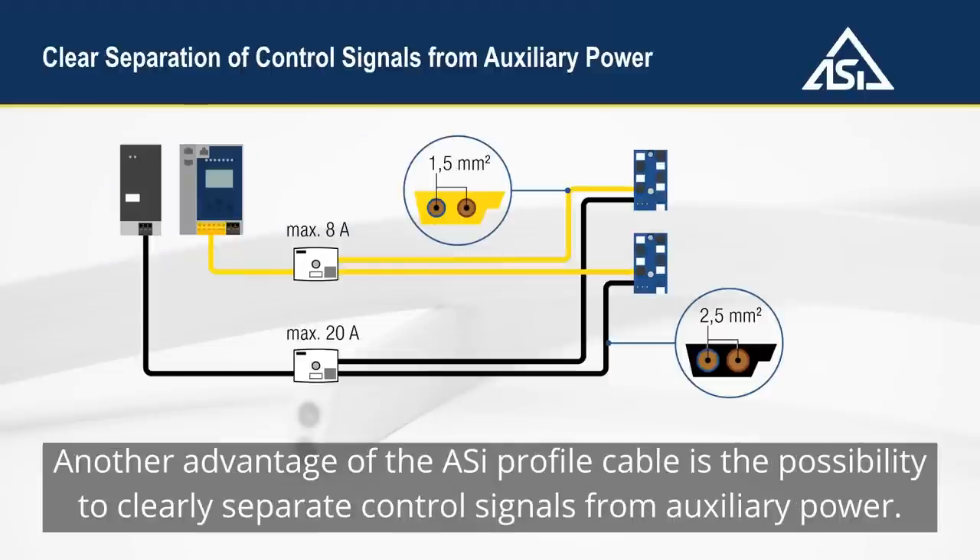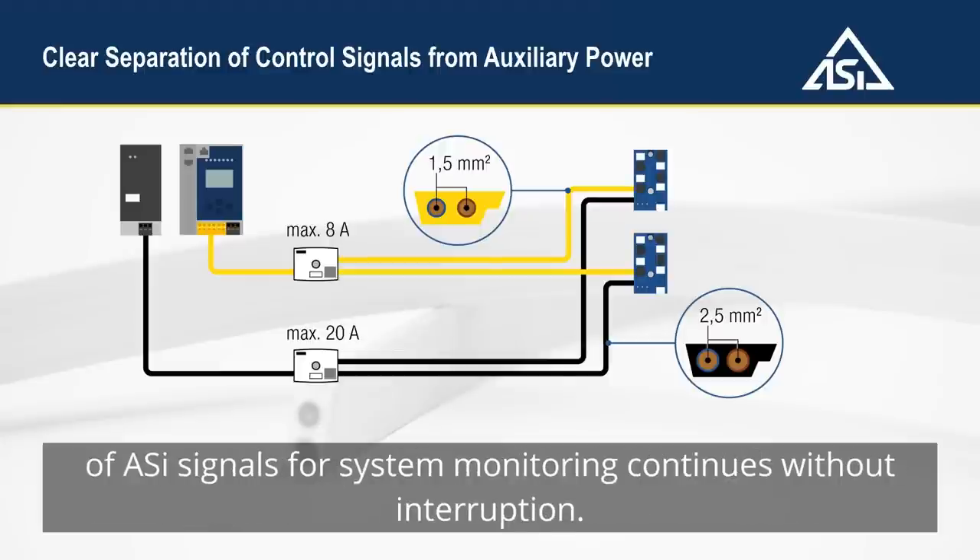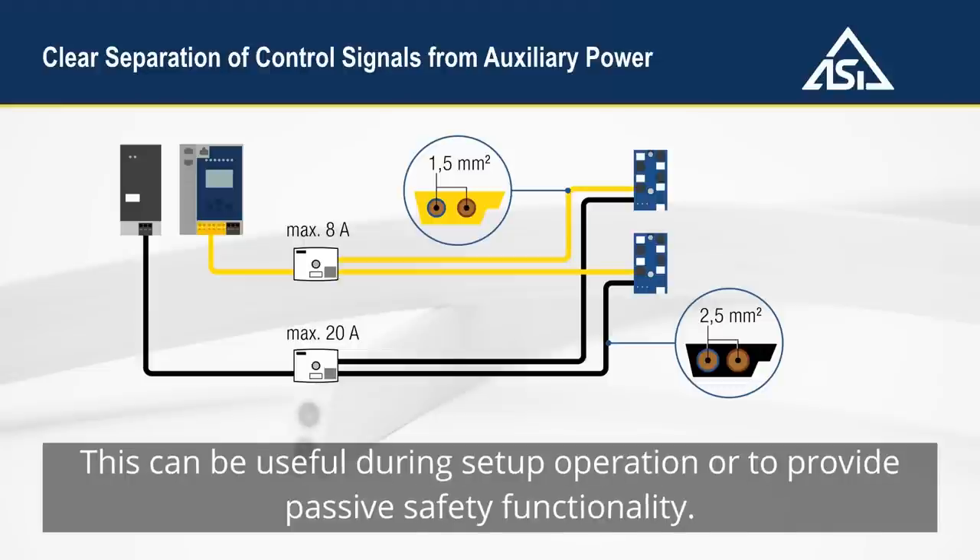Another advantage of the ASi profile cable is the possibility to clearly separate control signals from auxiliary power. This separation makes it possible to safely switch off the aux supply in a targeted manner while the transmission of ASi signals for system monitoring continues without interruption. This can be useful during setup operation or to provide passive safety functionality.